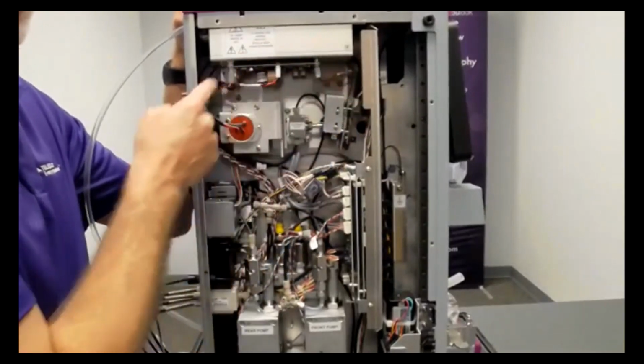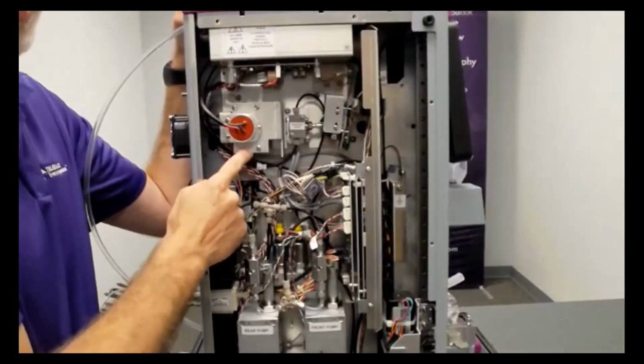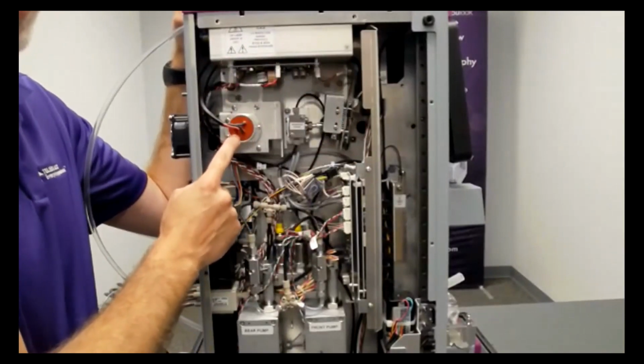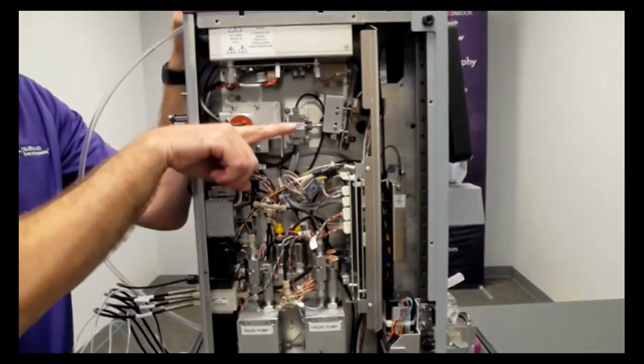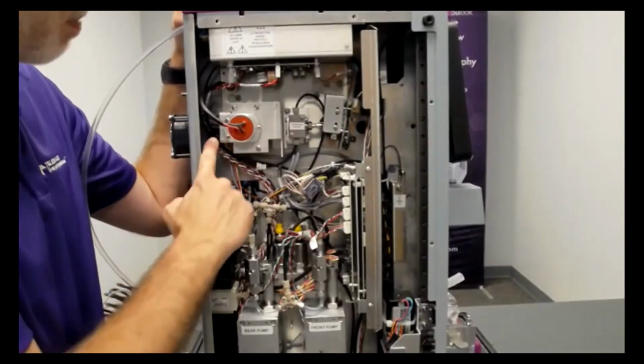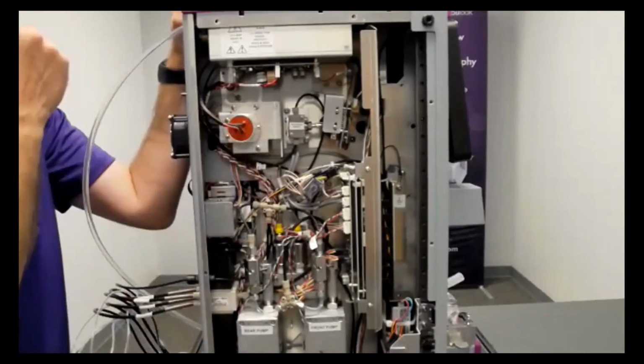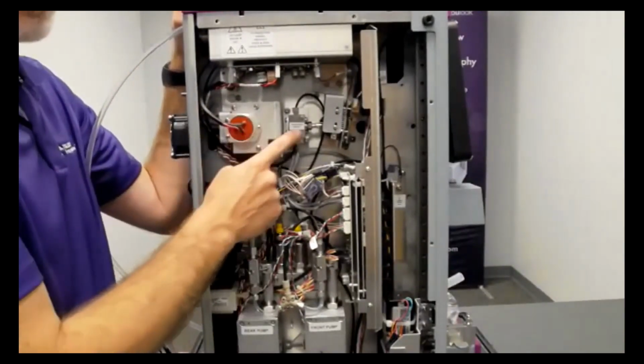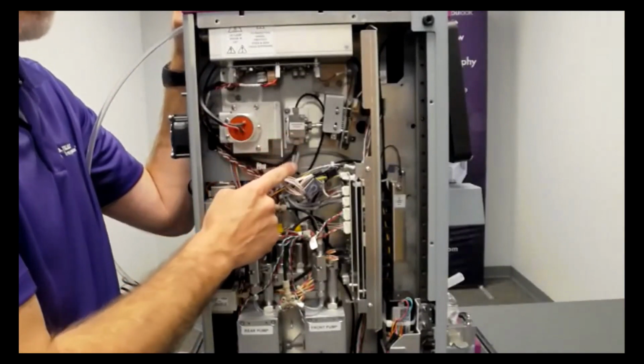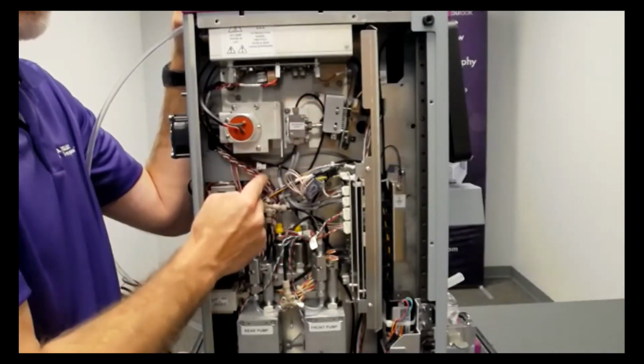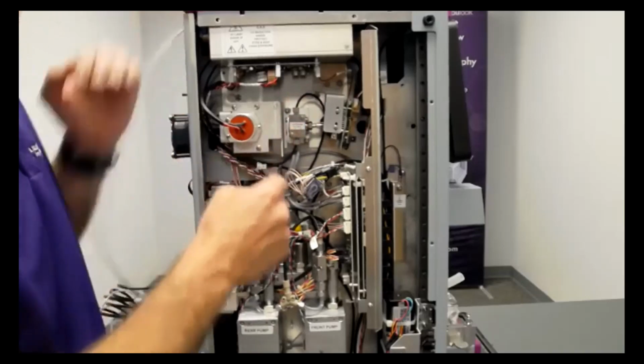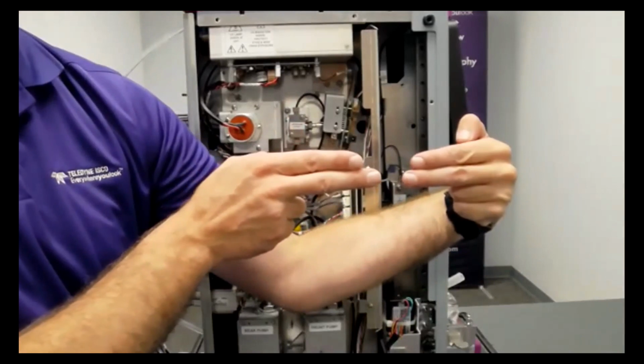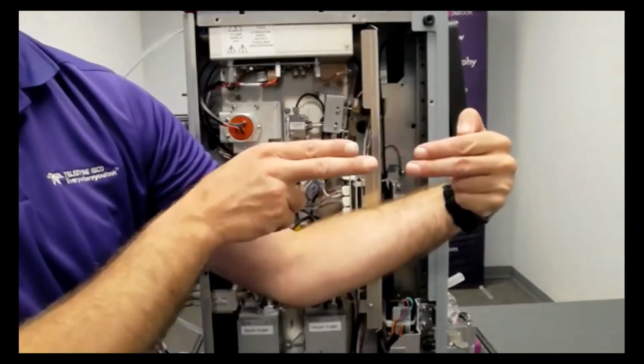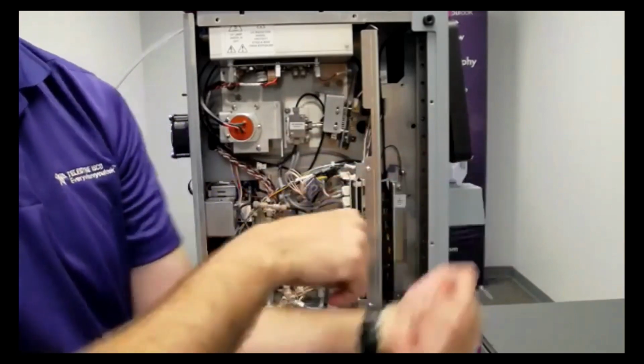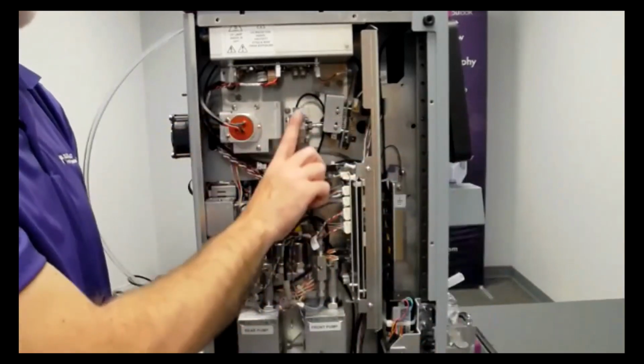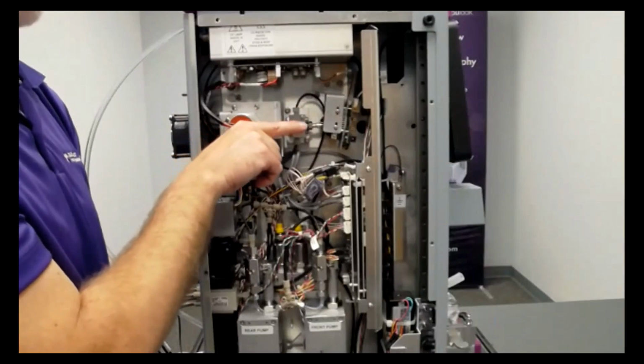Now this is the optical assembly up here. This is that lamp that we've talked about. It'll need replaced. Here's the fan that blows onto it. Okay, you can't see that thermal sensor, but it's back here. I'll show it to you when we take this out. But this lamp shines a light through this, the flow cell, and you see these black lines. This carries the solvent and sample to the flow cell. So there's, like I was saying, there's a gap there with those quartz rods. The solvent comes through the gap. The light shines through the rods. So as the light shines through here, you got solvent coming up here. It absorbs at certain wavelengths.